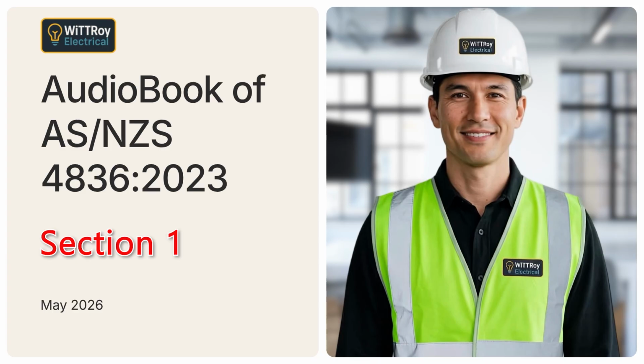Clause 1.4.25. Isolation, isolating function. Isolation is the function used to cut off supply from the whole installation or from a separate part of it by separating it from every source of electrical energy for safety reasons. In simple terms, isolation is about making the work area safe by removing the supply properly. Clause 1.4.26. Isolator. An isolator is a safety device that provides suitable separation in the open position for the voltage and insulating medium involved. The important point is that an isolator must create a safe break when it is open.